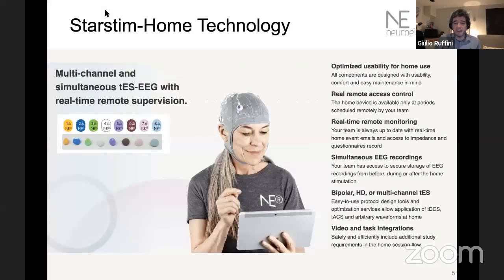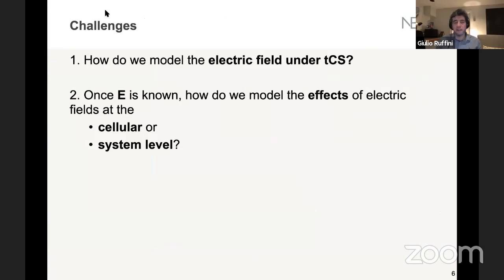So the technologies that we have at Neuroelectrics include multi-channel brain stimulation systems that are now usable for home use. They can also collect EEG, and they provide an opportunity, but also a challenge, because there are many parameters to be set in these stimulation protocols, many choices for the types of current that you can apply, tDCS, tACS, or tRNS, or actually custom waveforms, how many sessions you want to apply, how you can use EEG to better adjust stimulation protocols, and so on. So this is an opportunity and a challenge, and this is the rationale for my interest and for the interest of our company in developing solutions.